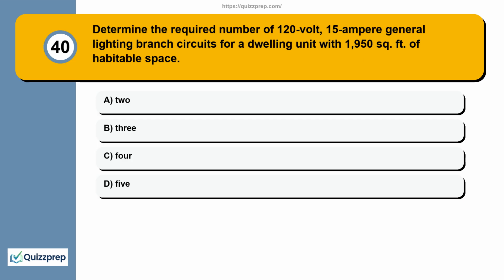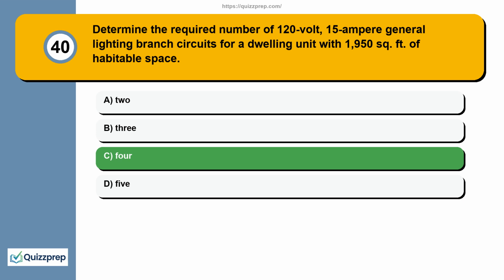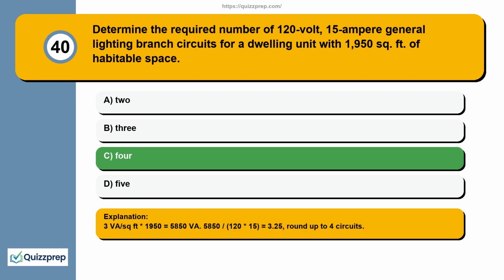Question 40. Determine the required number of 120 volt, 15 ampere general lighting branch circuits for a dwelling unit with 1,950 square feet of habitable space. 2, 3, 4, 5. 3 VA per square foot times 1,950 equals 5,850 VA. 5,850 divided by (120 times 15) equals 3.25, round up to 4 circuits.